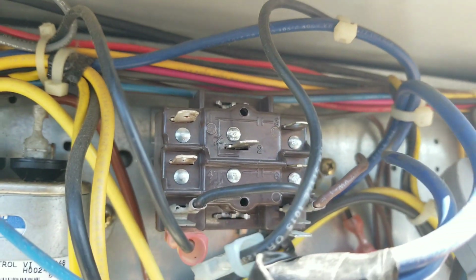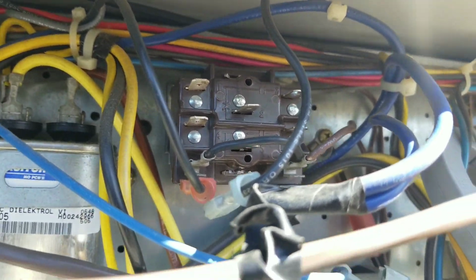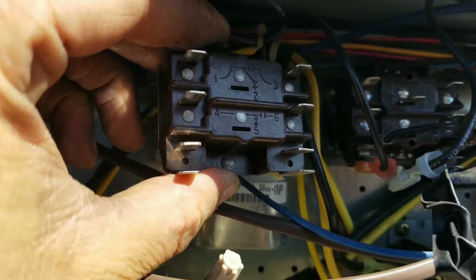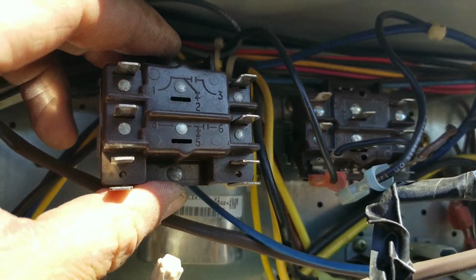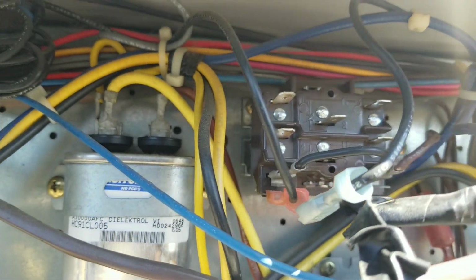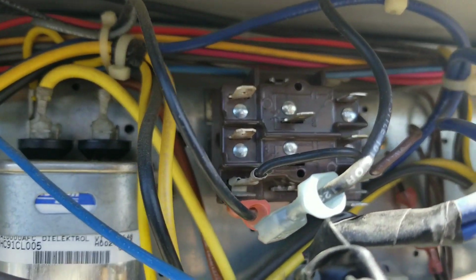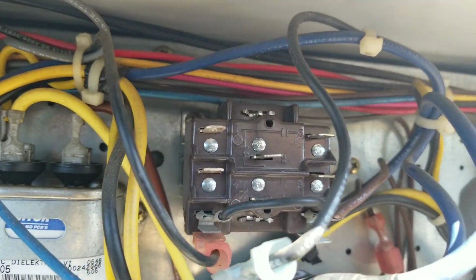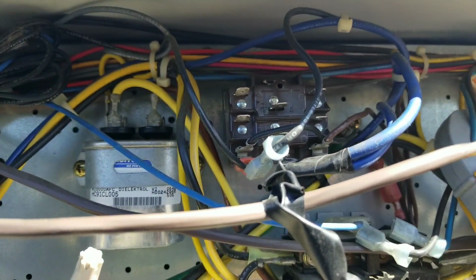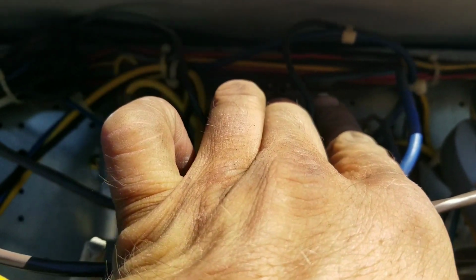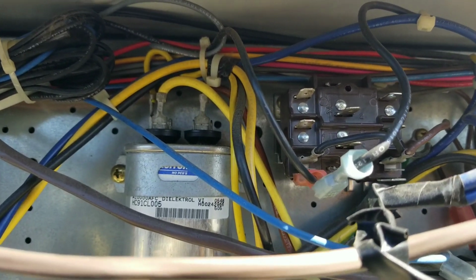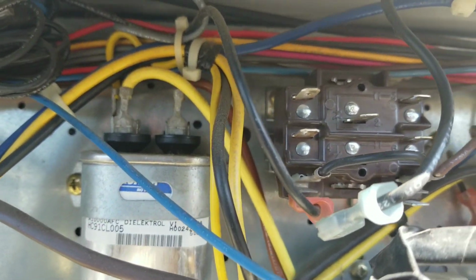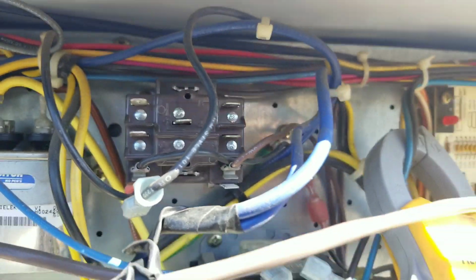We have our new switching relay installed right there. It's a little bit different than the old one. If you'll notice, the new one has a terminal for 2 and 5. Don't be too concerned about that. 2 and 5 is just a normally closed terminal from 1 and 2, and then also from 4 and 5. I don't use that for this particular setup, so we're not gonna do anything with that. But what we are gonna do is I'm gonna power it back on. And I'm gonna check for continuity across my top 2 and my middle 2 terminals. 1 and 5, or excuse me, 1 and 3 should have continuity, and 4 and 6 should have continuity once we power it up.